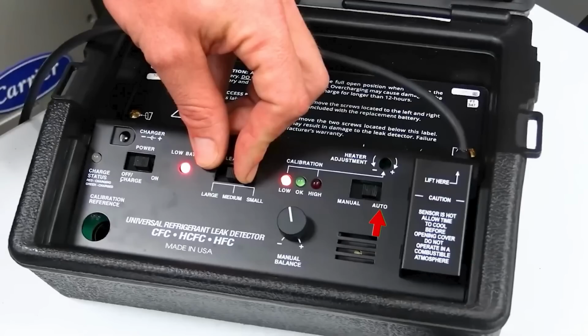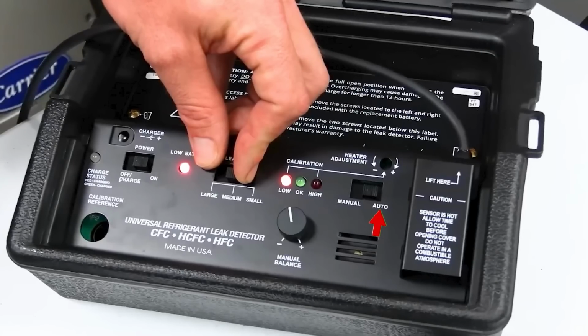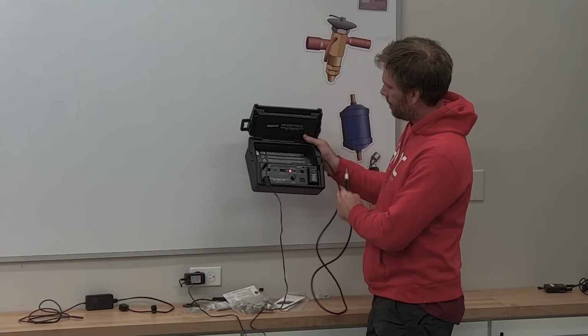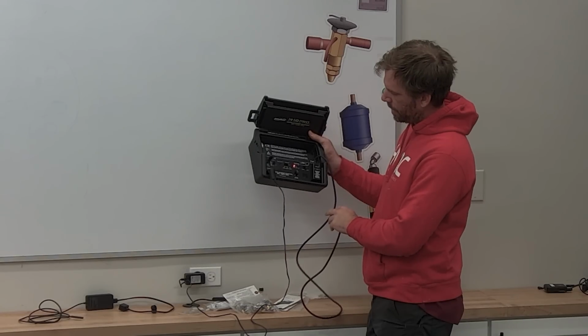It could be in the direct return where copper's running down next to the box. Then we either have a leaking box or no box at all, and it's all just floating in that area. You don't want to just pick up a hit and condemn a coil, right? So you can move it to large and then slowly get closer to your leak. That way, change the sensitivity if you're not picking up anything. The other feature that they have on here, which is auto, basically does the same thing that I'm describing between going large, medium, and small.